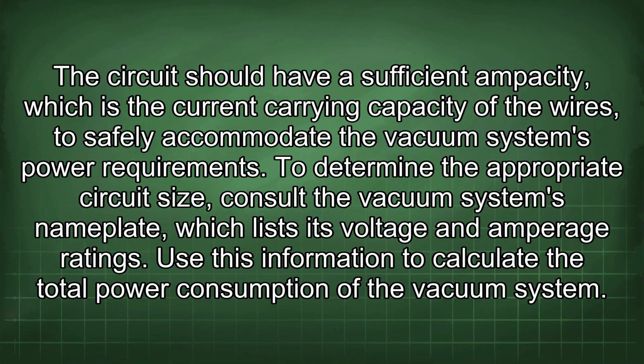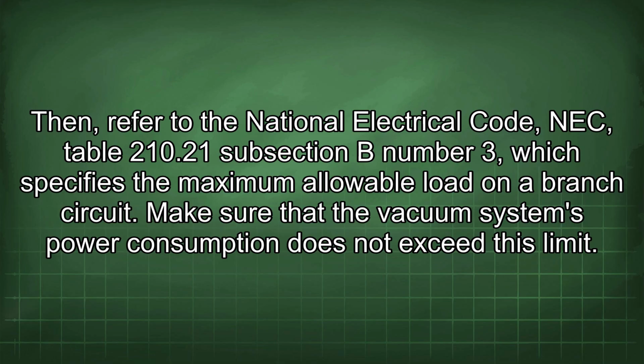To determine the appropriate circuit size, consult the vacuum system's nameplate, which lists its voltage and amperage ratings. Use this information to calculate the total power consumption of the vacuum system. Then, refer to the National Electrical Code, NEC, Table 210.21(B)(3), which specifies the maximum allowable load on a branch circuit. Make sure that the vacuum system's power consumption does not exceed this limit.